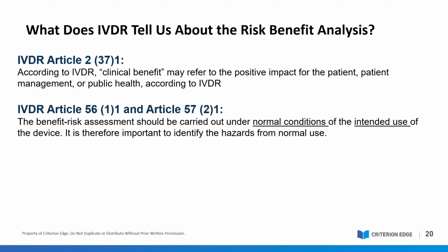That's because the benefit of an IVD medical device lies in its ability to provide accurate medical information on patients where appropriate and should be assessed against other medical information obtained through other diagnostic options and technologies. Whereas the final clinical outcome for the patient is dependent upon those further diagnostic or therapeutic options, which may or may not be available. So rather than requiring each individual benefit and risk to be compared against each other one by one, the regulations for IVDR define the benefit-risk determination to be the overall determination. So where an individual critical risk may not meet the initial acceptance criteria, residual risk should be justified and addressed in your description within the risk-benefit analysis.